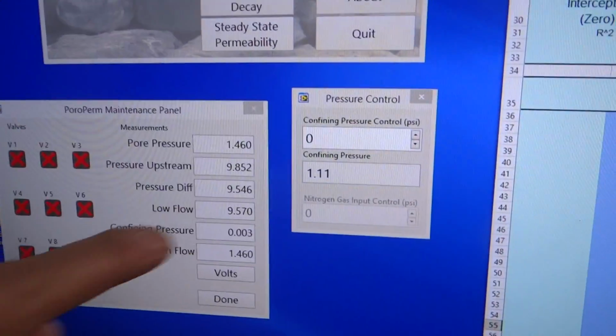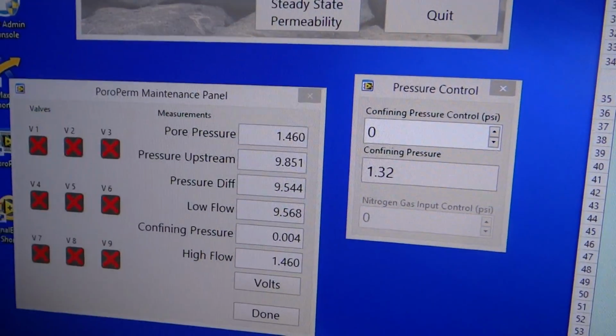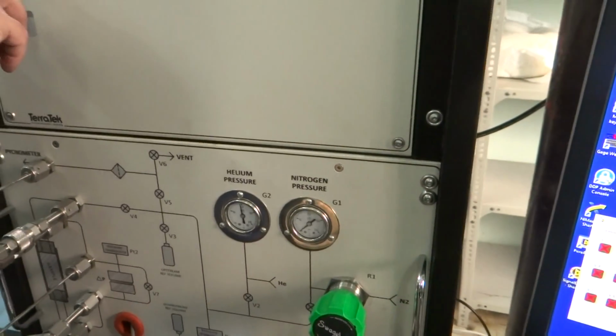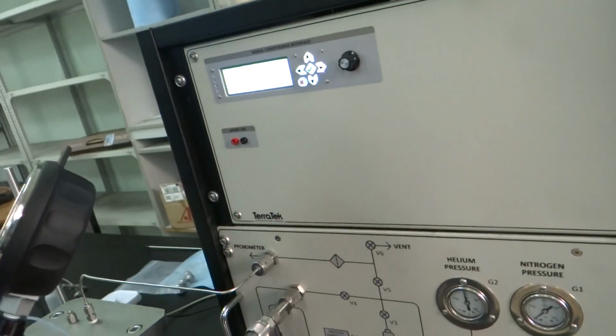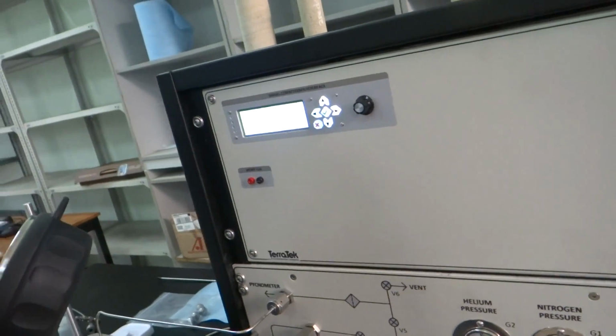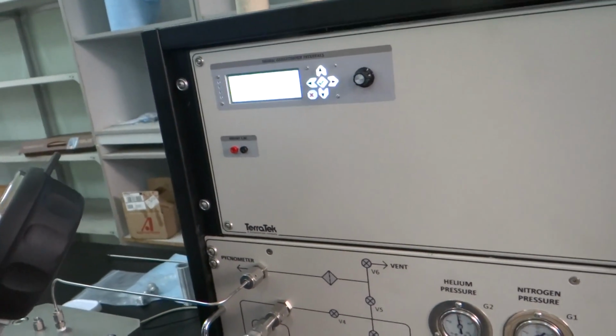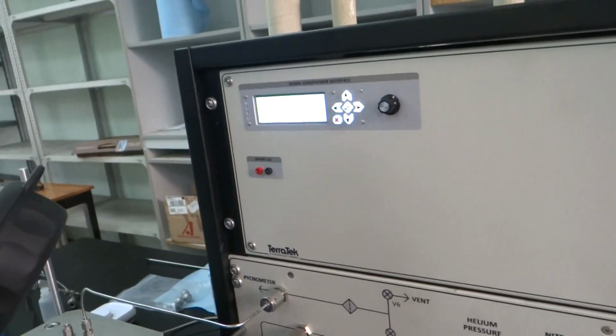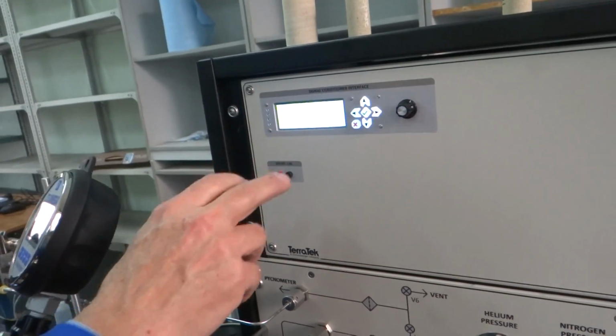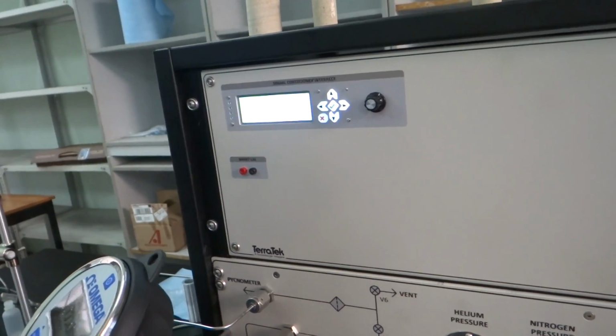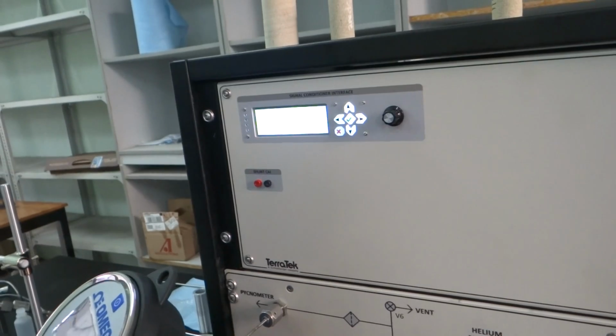So it should be a little bit less than 10, so 9.5. If not, then you have to adjust the gain until it's less than 10 volts. Less than 10 volts. Okay. And then you'll relieve the pressure.